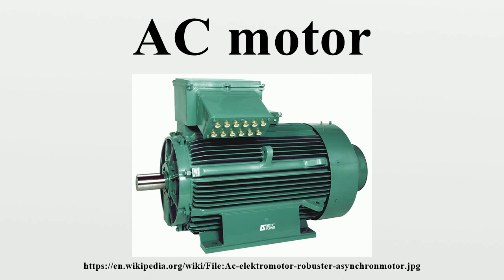Split-phase motor. Another common single-phase AC motor is the split-phase induction motor, commonly used in major appliances such as air conditioners and clothes dryers. Compared to the shaded pole motor, these motors provide much greater starting torque. A split-phase motor has a secondary start-up winding that is 90 electrical degrees to the main winding, always centered directly between the poles of the main winding, and connected to the main winding by a set of electrical contacts.